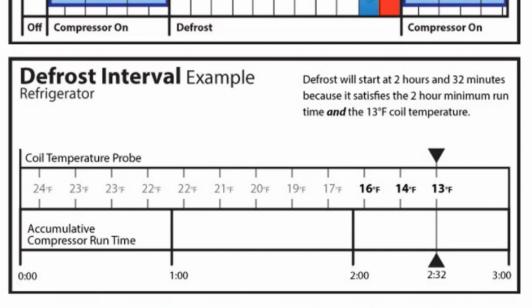We hit that 2 hour mark, but we're only at about, let's say, 16.3 degrees on that evaporator coil temperature. So we're not going to go through a defrost at that time. So the compressor runs for a little bit longer. Finally, after a little over 2.5 hours of compressor runtime, we hit the magic coil temperature here at 13 degrees. That's when it's going to initiate the defrost. So if we hadn't hit that 13-degree mark, we made it all the way to 3 hours, that's when we were going to go into defrost on that one.